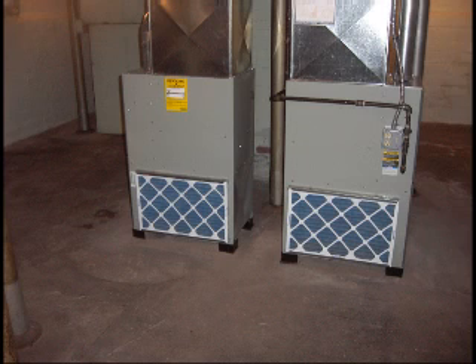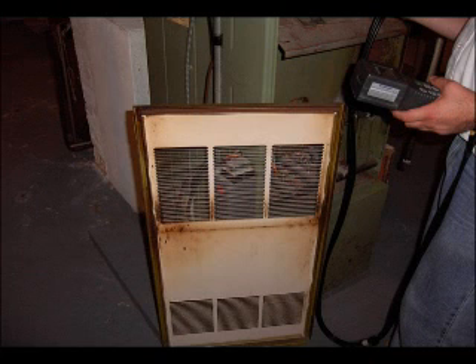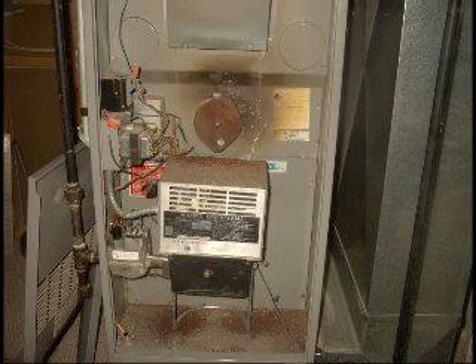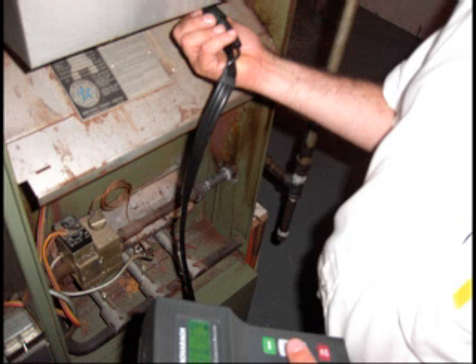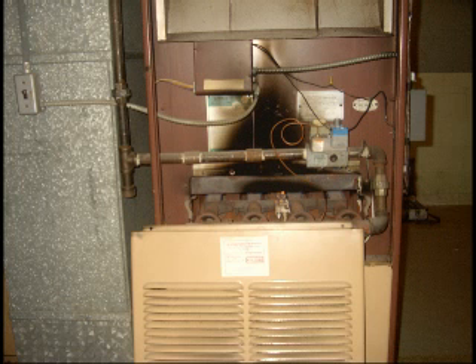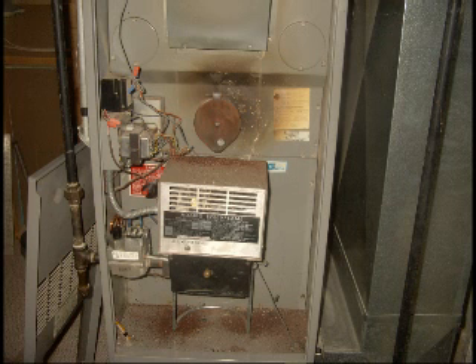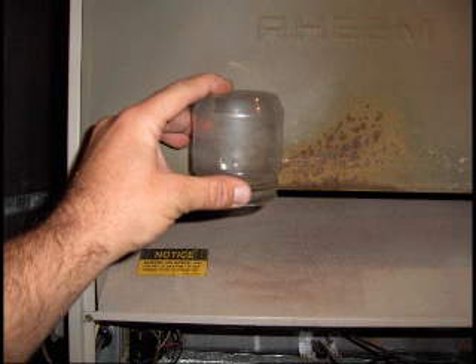And when it spills back into the water heater, you have incomplete combustion, and that creates a lot of carbon monoxide. And this is the same for the furnace. Go to the furnace. If there's stains on the upper portion, well, you've got no draft. If there's stains at the bottom, then you have too high a draft. Rust stains on gas fired systems, oil burners, or any type of fossil fuel burning system is an indication of a major problem.